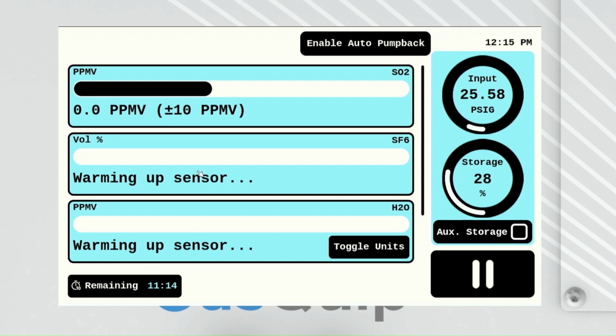So as this SO2 sensor runs here, we can see that we have a loading bar to show us how much time is left on the SO2 test. Below that, you have the 0.0 ppmv, which is the reading. And then here in parentheses, we have listed the accuracy of the sensor. So this is a 0 to 500 ppmv range sensor, and the accuracy is plus or minus 2%, which translates to plus or minus 10 ppmv.